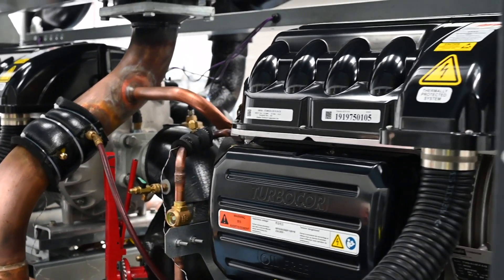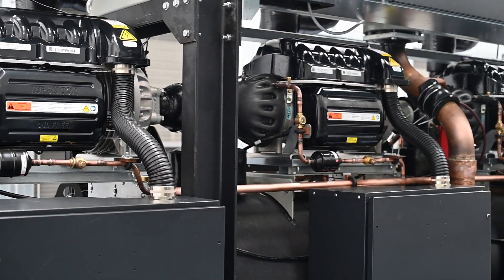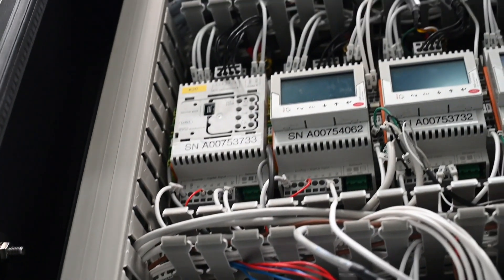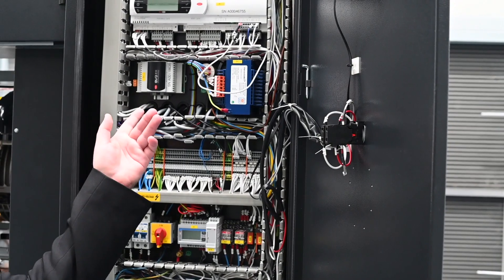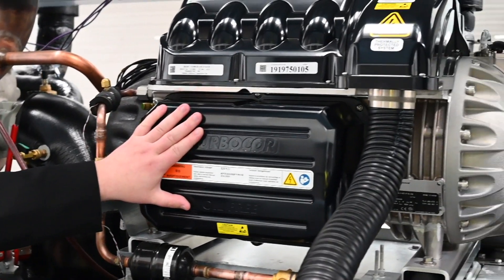The TCW Hydro is the first product that we've got using a new controls platform. We've got years of experience now working with Turbocor compressors, which are very complex pieces of equipment, and being able to build this software up from scratch has given us the ability to take all of those lessons that we've learned and build software that's nice and clean and efficient, with a lot of new features that we weren't able to do before, such as synchronized compressor starts. This means that following a power outage, for instance, this chiller is able to start much quicker than any other products using this compressor technology.